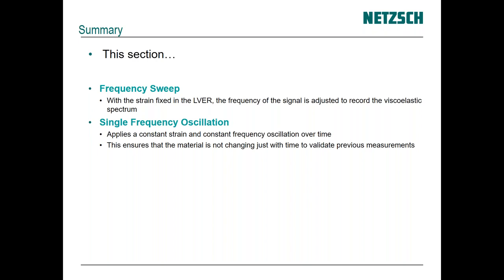In summary: for frequency sweeps, if you hold strain fixed within the linear viscoelastic region the frequency of the signal is adjusted to record the viscoelastic spectrum, giving a better understanding of material behavior. For single frequency oscillation with constant strain monitored over time, you can see what happens to the material with time — how long it takes to build structure, whether structure recovers after breaking, and for cross-linking materials like glue, how long it takes to reach the point where elastic behavior dominates.